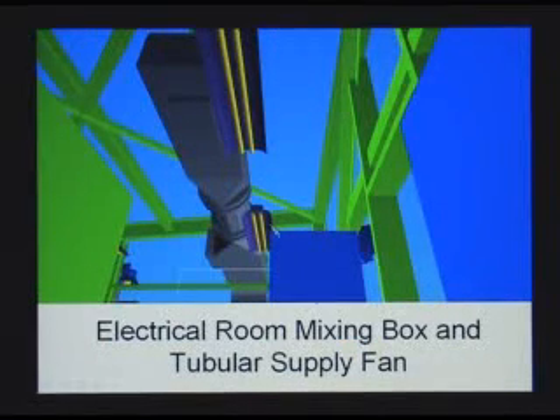This is our mixing box. And in the electrical room we provide a mixing box, which brings outside air and mixes with inside room air, so we mix the air. This way we keep the temperature high enough. If you bring outside air all the way, you're going to freeze. So we have mixing boxes here to mix both inside air and outside air.